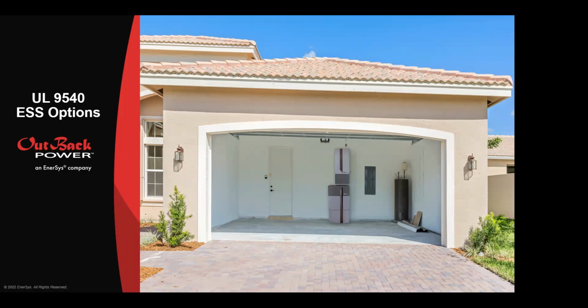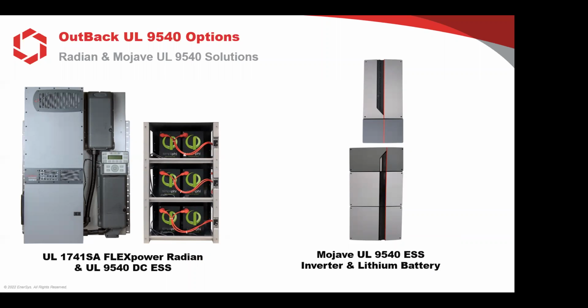Okay, so now we're going to talk about what options you have for OutBack. So we have our FLEXpower Radian. This is basically our DC coupling option. And we have a UL 9540 DC ESS. That's this rack, but it was certified with SimpliPhi batteries. It got that listing, so only SimpliPhi batteries work with this battery rack. But this is an example of a DC ESS. So with this solution, you can get the SimpliPhi batteries through altE and everything else from OutBack. That is our DC ESS. Mojave is a UL 9540 ESS. So these are your 2 options from OutBack for UL 9540.